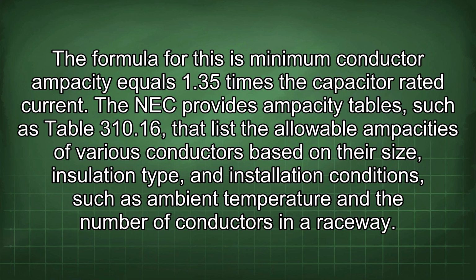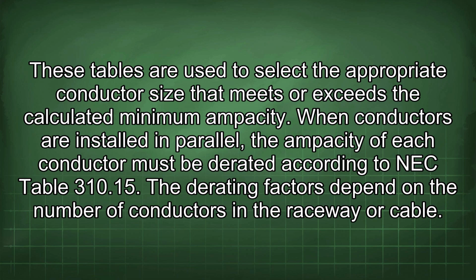The NEC provides ampacity tables such as Table 310.16 that list the allowable ampacities of various conductors based on their size, insulation type, and installation conditions such as ambient temperature and the number of conductors in a raceway. These tables are used to select the appropriate conductor size that meets or exceeds the calculated minimum ampacity. When conductors are installed in parallel, the ampacity of each conductor must be derated according to NEC Table 310.15. The derating factors depend on the number of conductors in the raceway or cable.